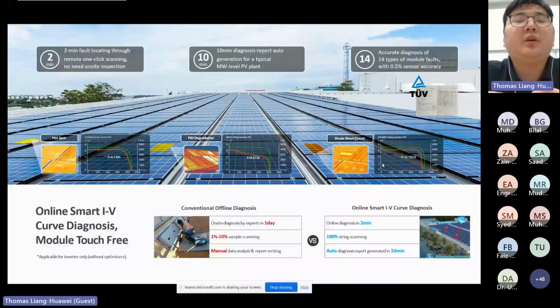So now what Huawei proposes is the smart IV curve technology. You just sit in your office and click the start button. Then the system will do a self-scan of the PV modules automatically. For a 100 megawatt PV plant, it's just 10 minutes. You will get 3 reports telling you what fault happened to the PV module, in which string, and any suggestion to repair or replace it. Those reports are automatically generated by the Huawei system. By now we can detect 14 types of PV module faults, with 0.5% sensor accuracy.